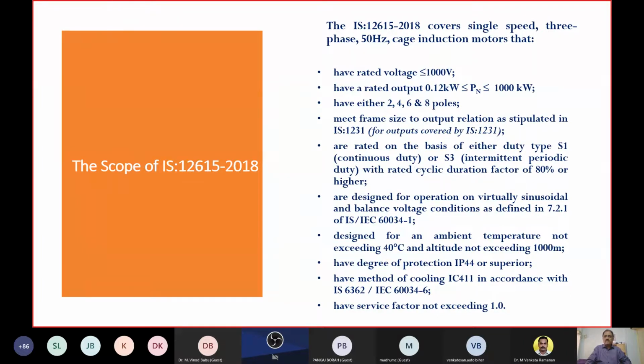Again, motors should be designed for an ambient temperature of 40 degrees centigrade and an altitude not exceeding 1000 meters. When the altitude exceeds 1000 meters, derating has to be applied. And when the ambient increases beyond 50, because motor manufacturers now adopt up to 50 degrees centigrade, beyond 50 again the standard is not applicable. These motors are generally provided in IP55, so the scope document includes motors of IP44 or higher. The method of cooling for these motors is according to IC 411, which is a self-cooled fan at the non-drive end of the motor. And the service factor is not exceeding 1.0.